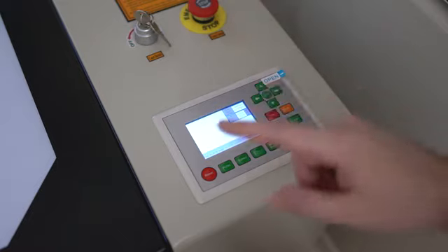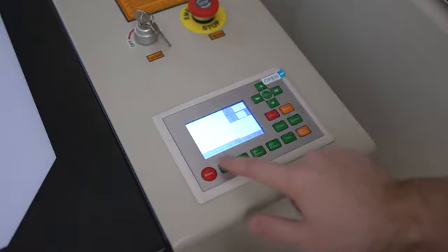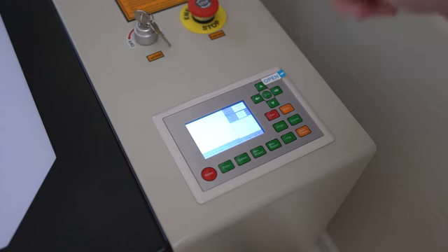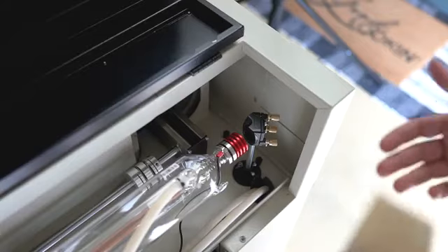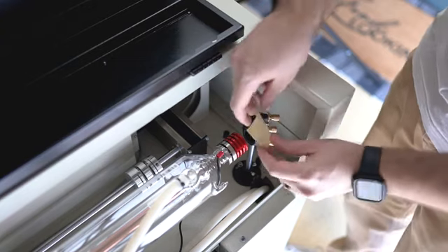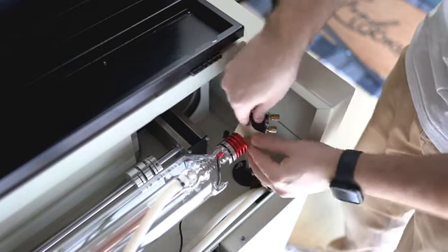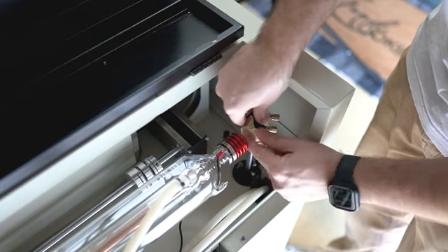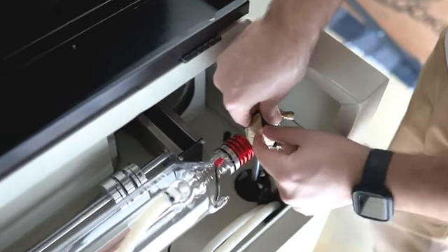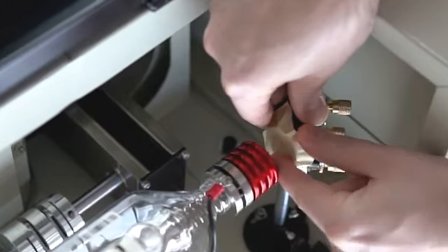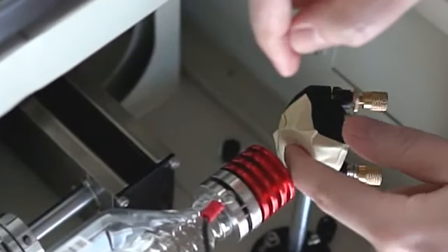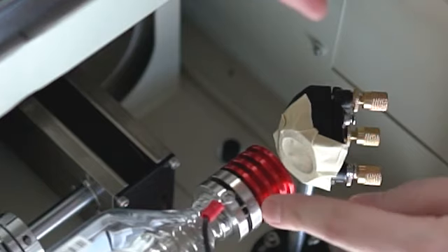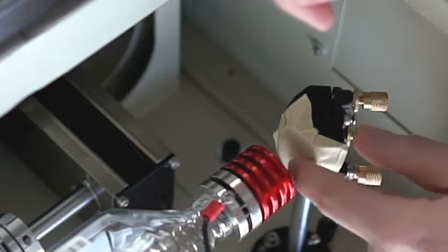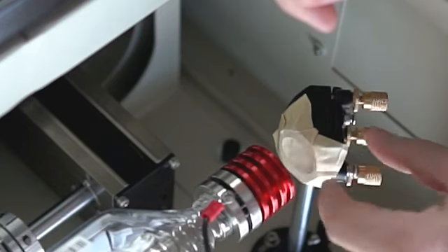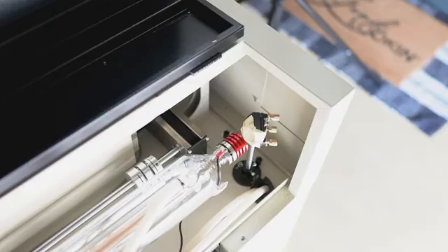Then what we're gonna do after we put the tape in place, we'll hit the pulse button, and that will send a laser pulse through the laser and all the system. So let's set up our tape. This is actually really easy. All we're gonna do is take one of our pre-cut pieces of tape, set it here across the mirror opening, and then press really hard inside that opening, and this is gonna create a little outline. That outline now helps you dictate where the center is gonna be. We want to make sure that as the laser leaves the tube and hits this housing, it's gonna hit the mirror straight in the center. So this is gonna help us identify that. All right, so it's all set up. I'm gonna hit the pulse button here.